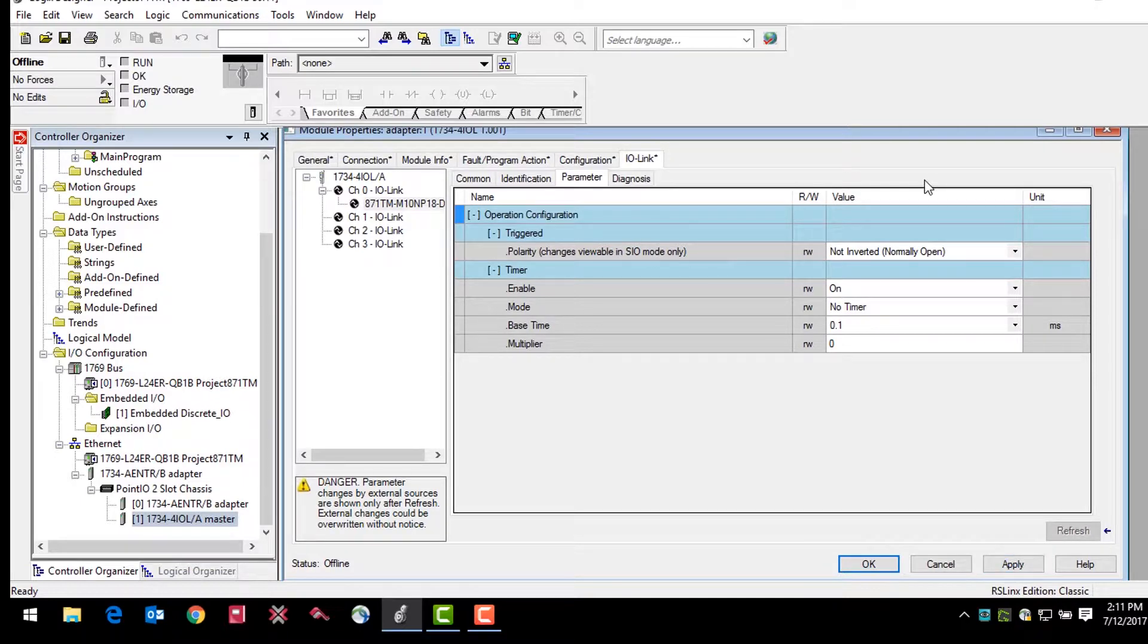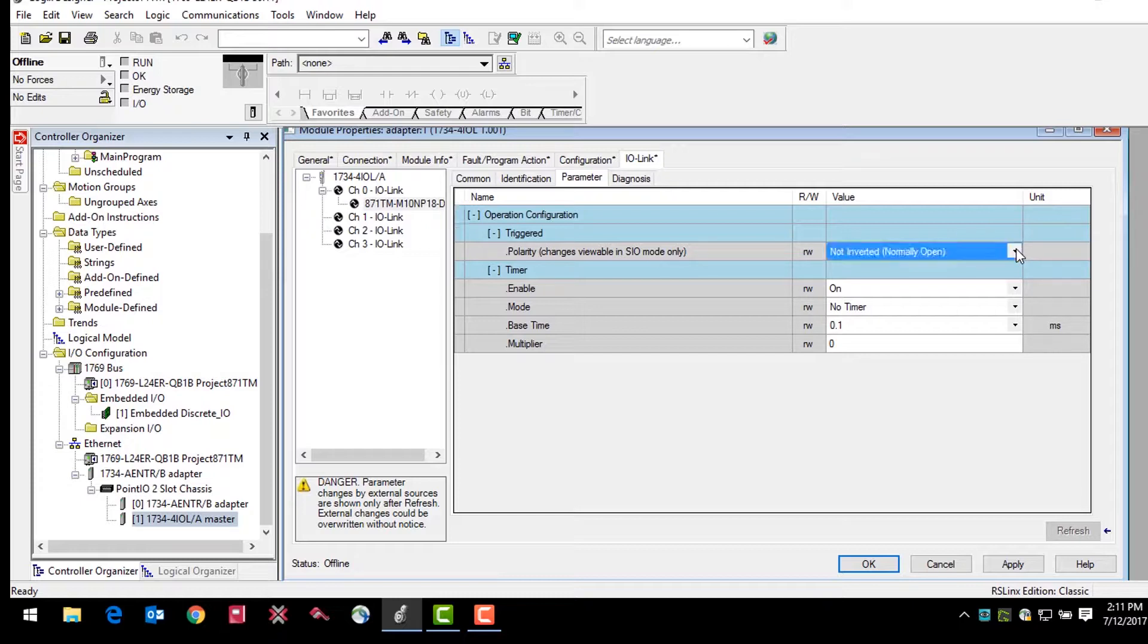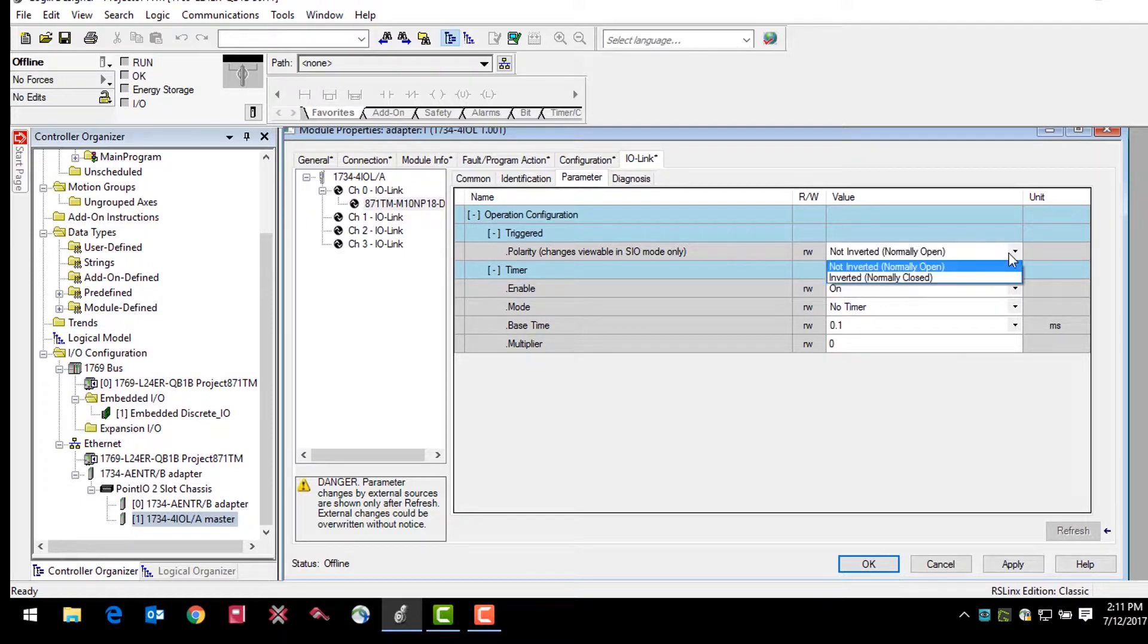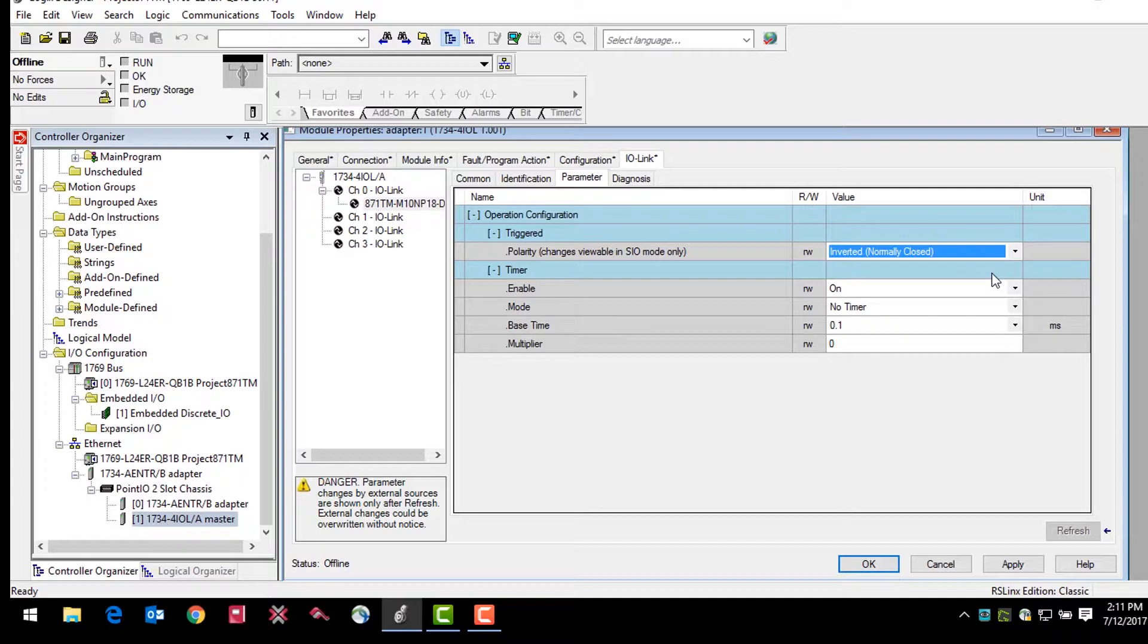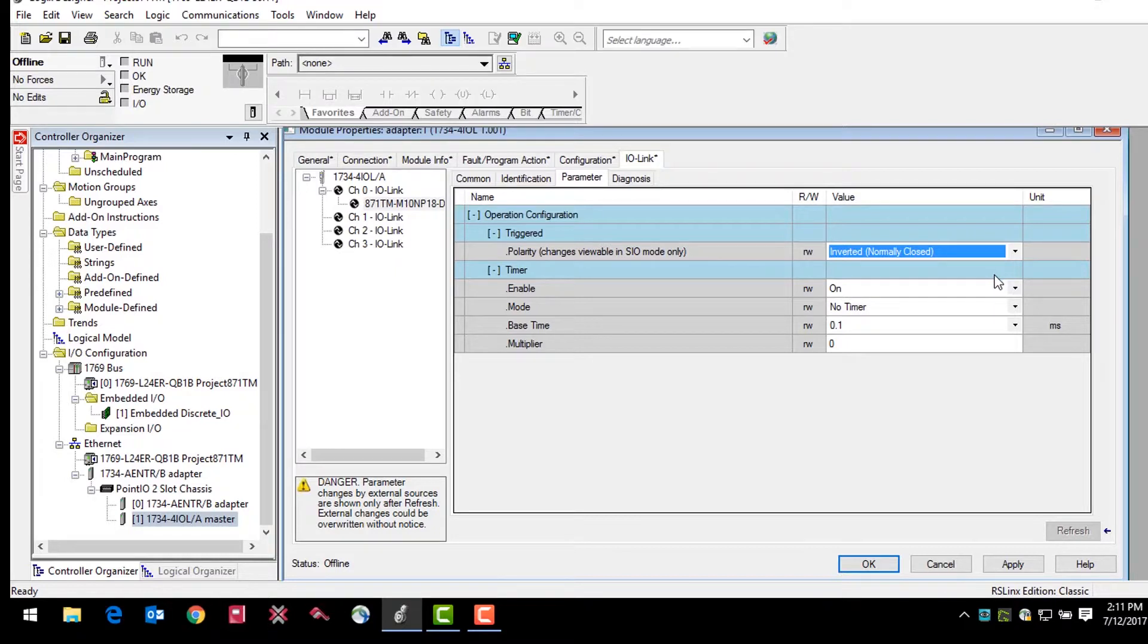The 871 TM sensor features the ability to change the output switching mode or the polarity parameter. The factory default mode is not inverted or normally open. When the sensor is in IO-Link mode, you can change the polarity parameter to inverted or normally closed. The ability to change these factory default settings that normally would be non-configurable is a huge benefit of the IO-Link technology.